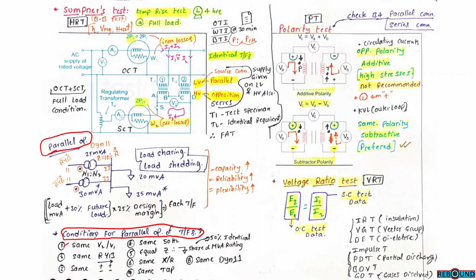One is the same V2 by V1 ratio or K ratio, same phase sequence RYB, same polarity, same frequency, equal impedance. This is for load sharing with reference to MVA rating. Same X by R ratio, same tap settings, and same vector grouping. These are the conditions for parallel operation of transformers.